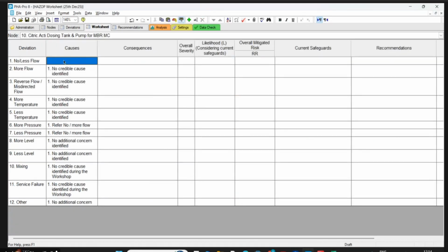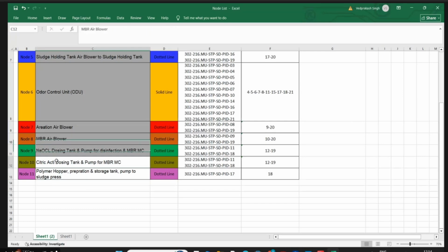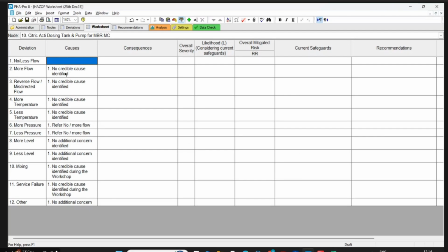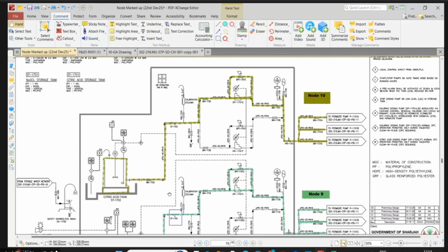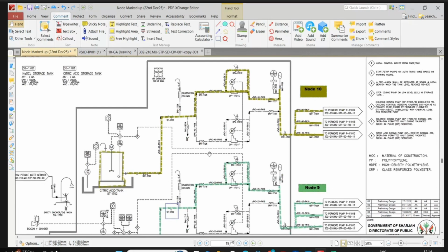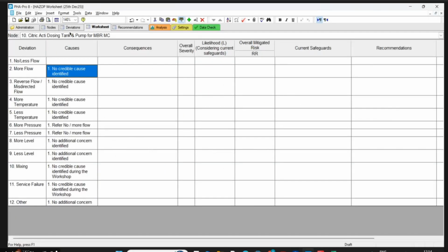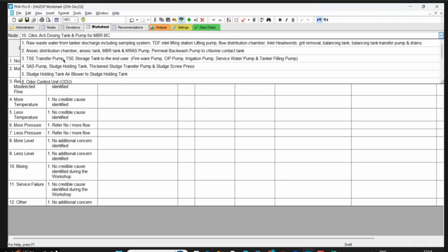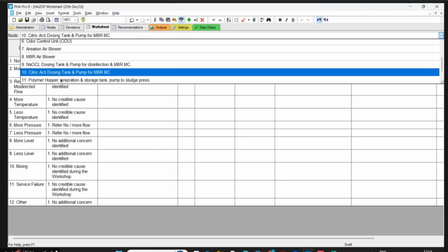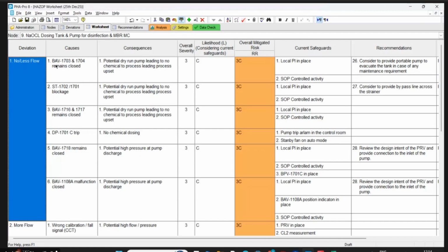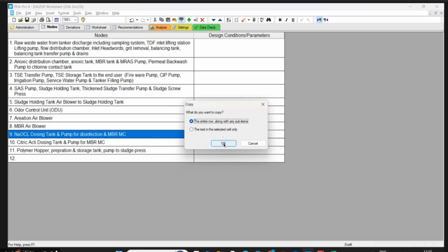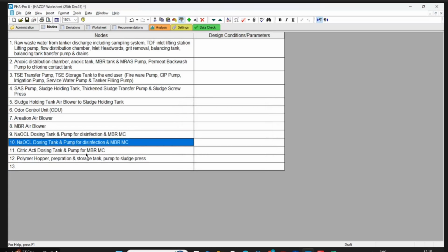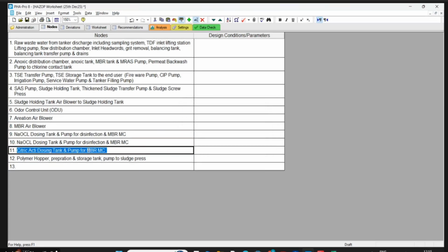As MBR. But this is a different type of form. The pipes are a different type. It is also shown as a PD pump, but it should be free discharge because it shall be discharged into the tank. It says PD pump, but it's a different type. It can be a PP centrifugal pump because you are just dosing into the tank.